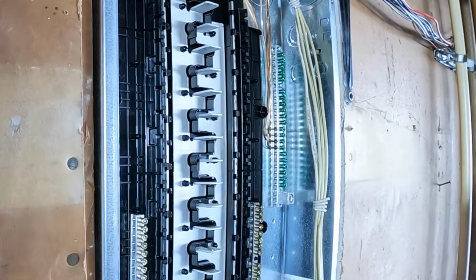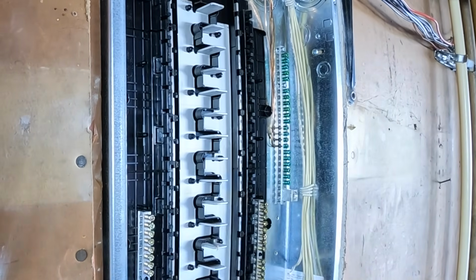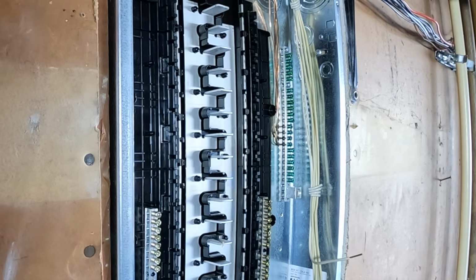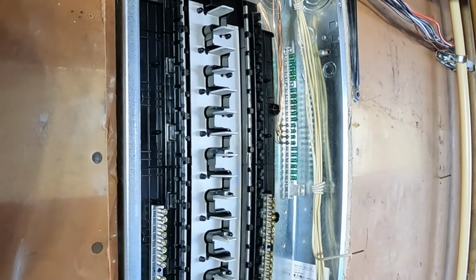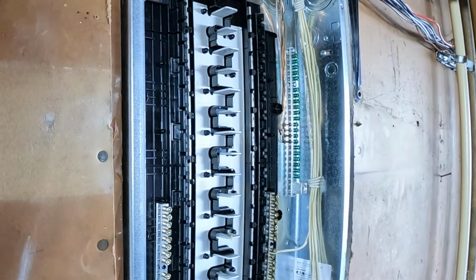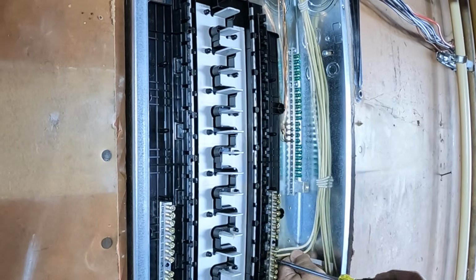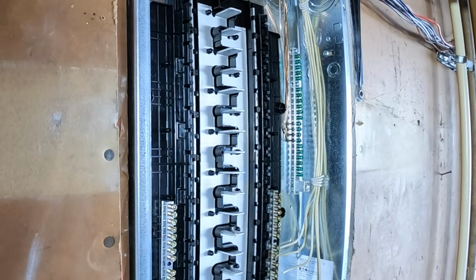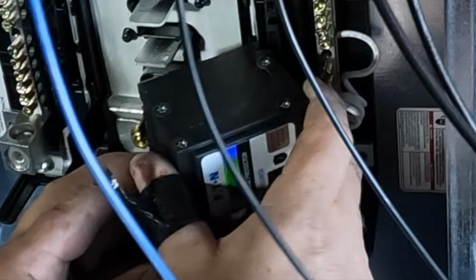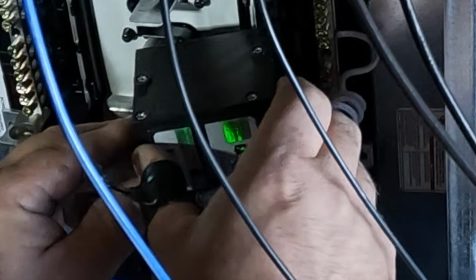The neutral conductors are current carrying conductors, so they go onto a different terminal bar. And of course, the main bonding jumper screw that comes with this panel has been removed, because we do not want to bond our grounded neutral to our equipment grounding conductor in a main lug only panel.